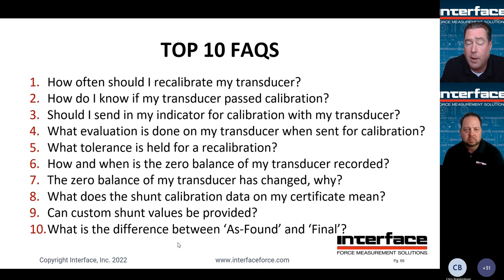We also provide a straight line conversion number that would indicate the force equivalent of that simulated output that you can use to scale instrumentation. It's getting less and less common in my personal experience for instrumentation to require that, but it can be a good reference check for load cell health. For example, being able to check load cell zero balance and then checking load cell shunt against a known cert can be a good indication of health of the load cell. So if you see deviation between your results that you're getting in the field versus the cert, that should be a flag.